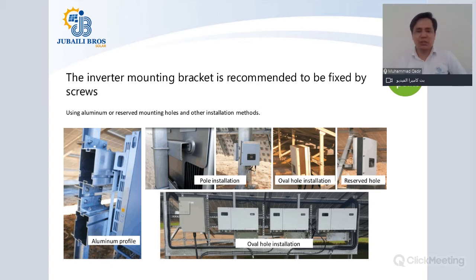In all these scenarios, one thing that must be taken care of is that the screwing is important. You can hang the inverter, yes, that will hold the inverter onto the top of that frame. But in the long run, the system installation could face severe wind blows, which could loosen the inverter connection to that frame and it may fall down. So one thing very important is that you must screw your inverter after hanging it onto the top of the frame of Huawei or the customized one which you have used.